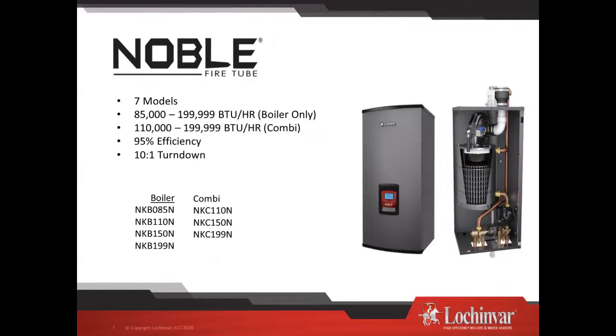There are three sizes to the Combi model, and the numbers in there will also tell you the BTU size. So it's also important if you're talking about parts, things that you might need, knowing what you have. So just a little nomenclature: an NKB is going to be a boiler only, an NKC is going to be a combination unit. The N or an L at the end will let you know what type of gas that boiler is designed around.